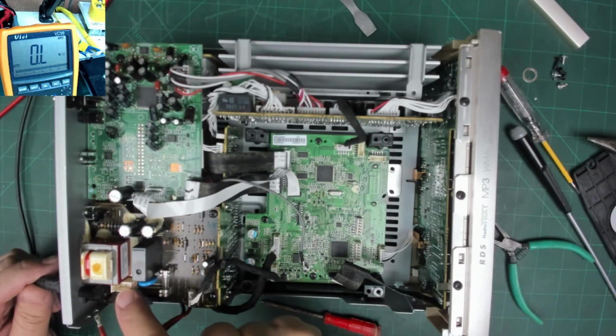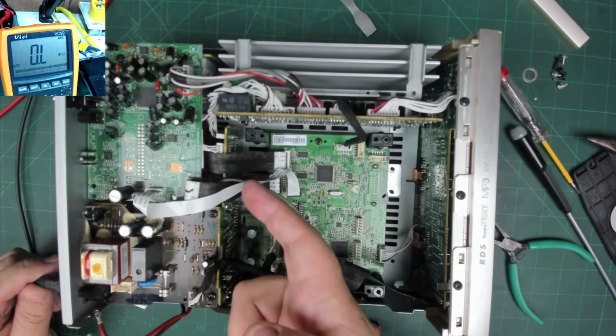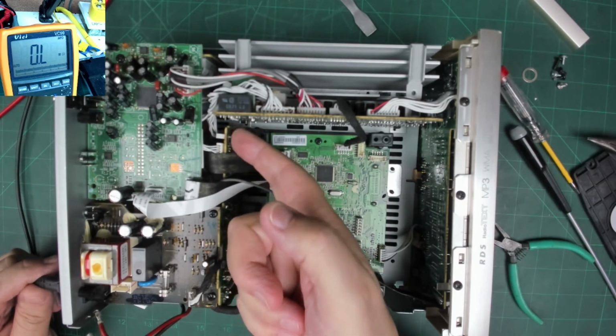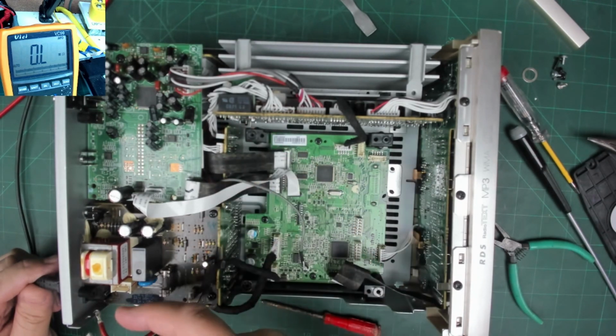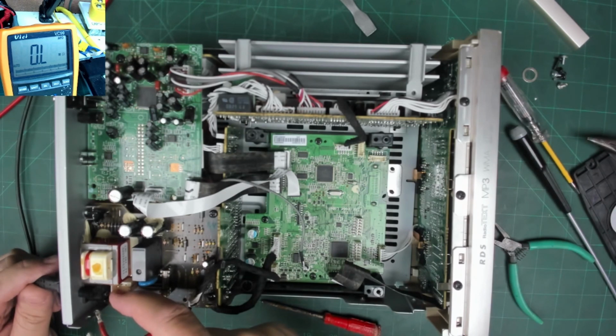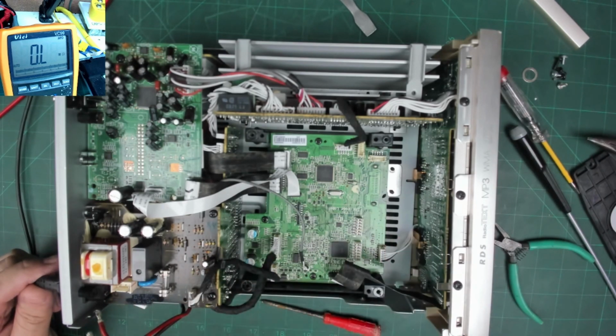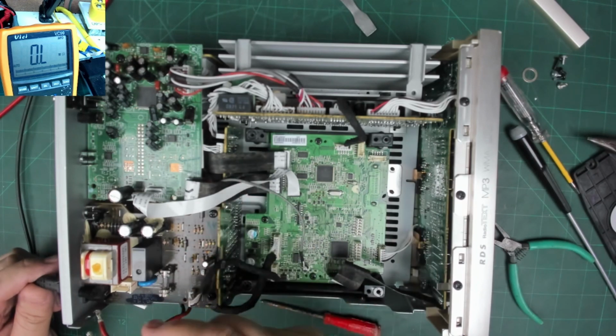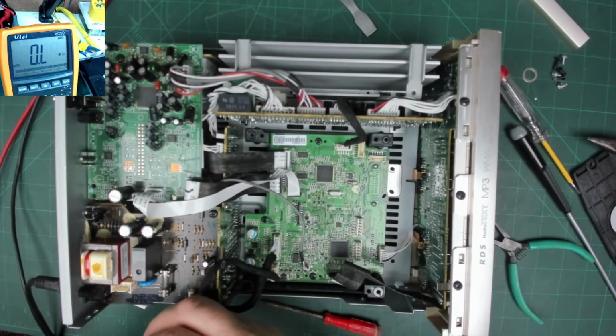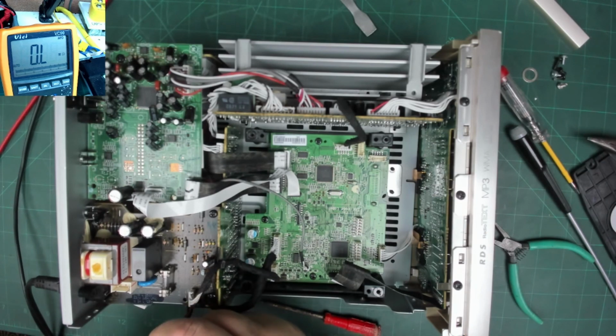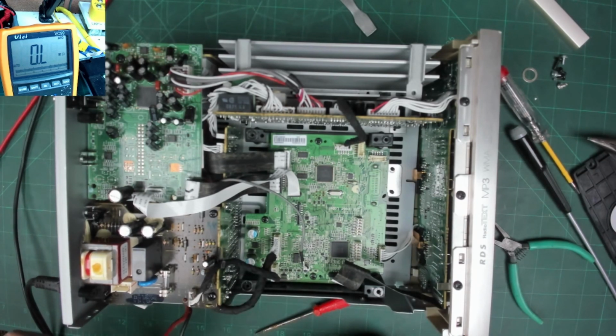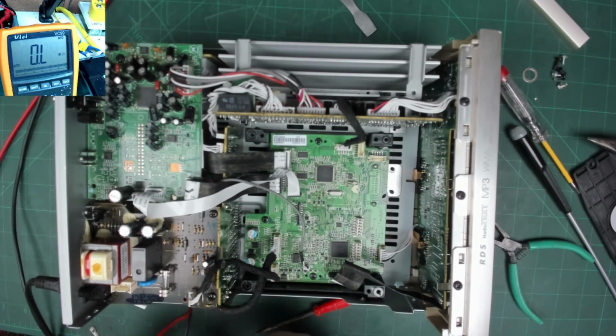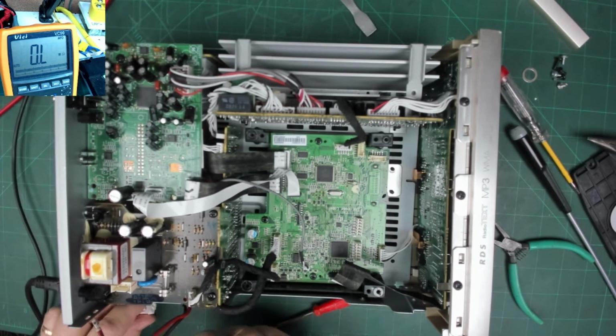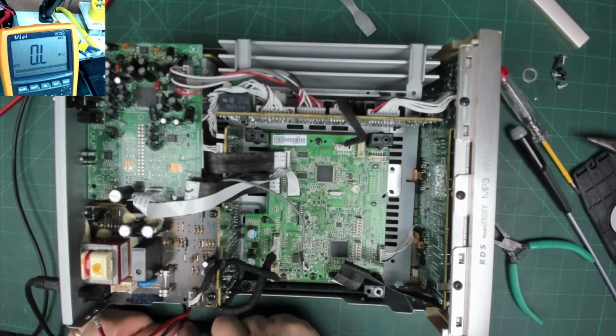But I was getting AC volts here all the time. I then thought, well, if we get AC volts there and we're getting nothing out here, which is the AC from the transformer, and this is on all the time irrespective of the electronic switching, there must be something wrong with the transformer. So, meter on ohms, across the transformer primary - nothing. Transformer's open circuit.